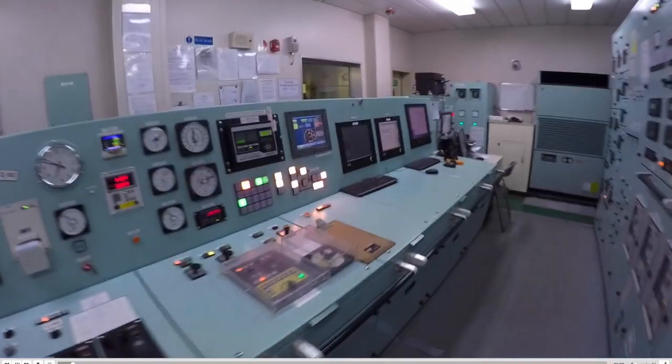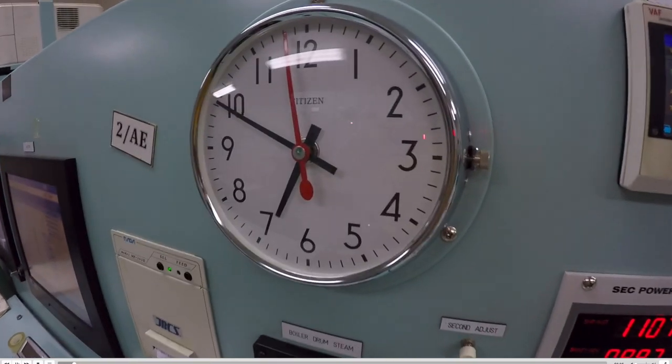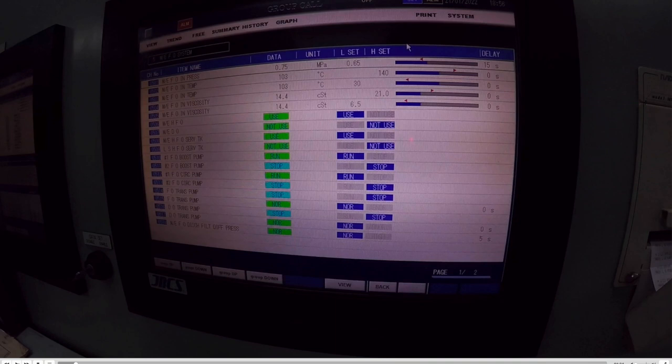And the most common problem of the vessels is the heating coils. Always you must be aware of the heating coils. So before you go on board, you need to check if the heating coils are working properly, and if they are not working, you should take some action to repair them. I have seen the same problem on almost all vessels. I have fixed that kind of problem, but I have seen that most engineers do not give attention to it. What they did was use only some tanks that have heating, and always use them. This is the solution that they give.